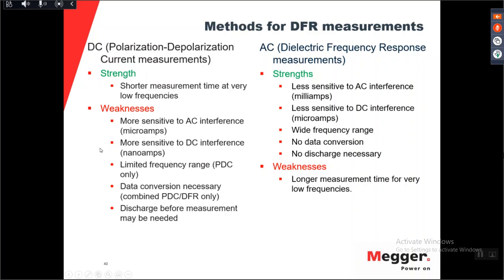The problem with the polarization depolarization current is that you also need to discharge the measurement before you can start to do your measurement. And if you take the discharge into account when you're doing your full measurement, the actual measurement time is more or less very similar. And since you need to discharge, you cannot repeat your measurement directly after you have done a polarization measurement. So you do your PDC measurement. When you're done, you need to discharge for the same amount of time as you took your measurement before you can repeat the measurement, or you will not get the same type of result. So there you have a big inaccuracy.